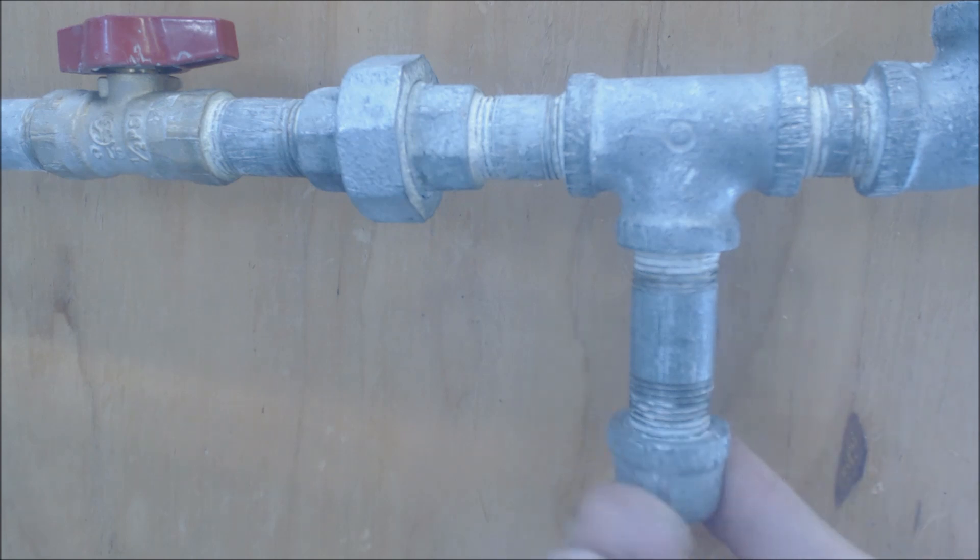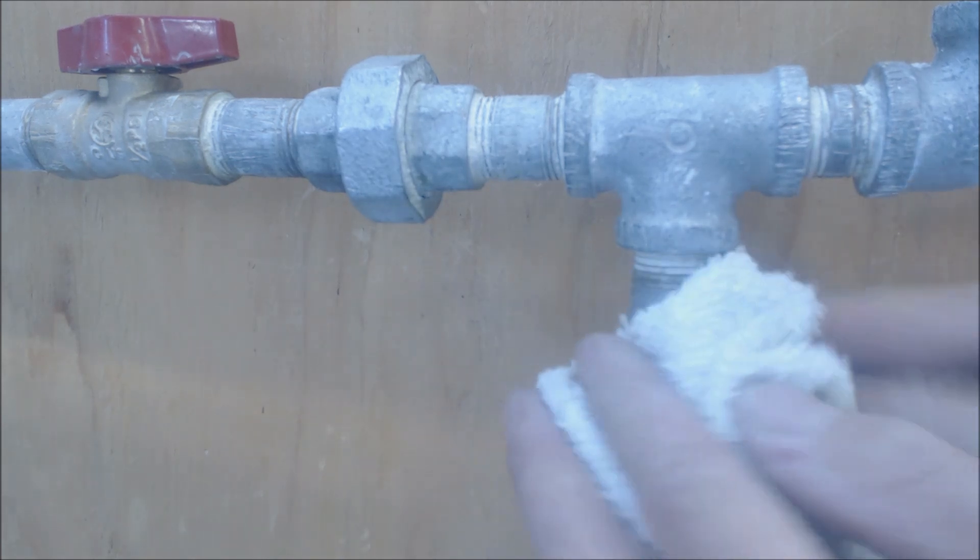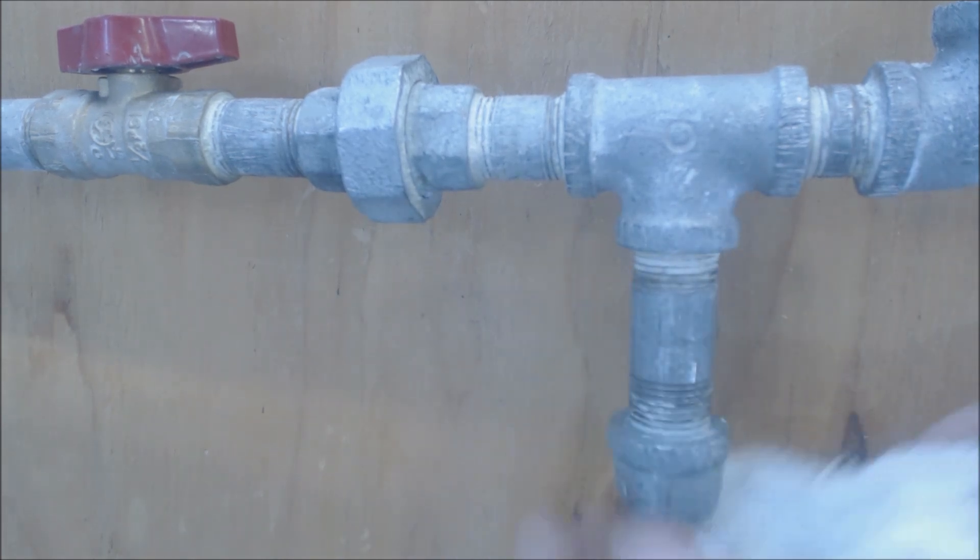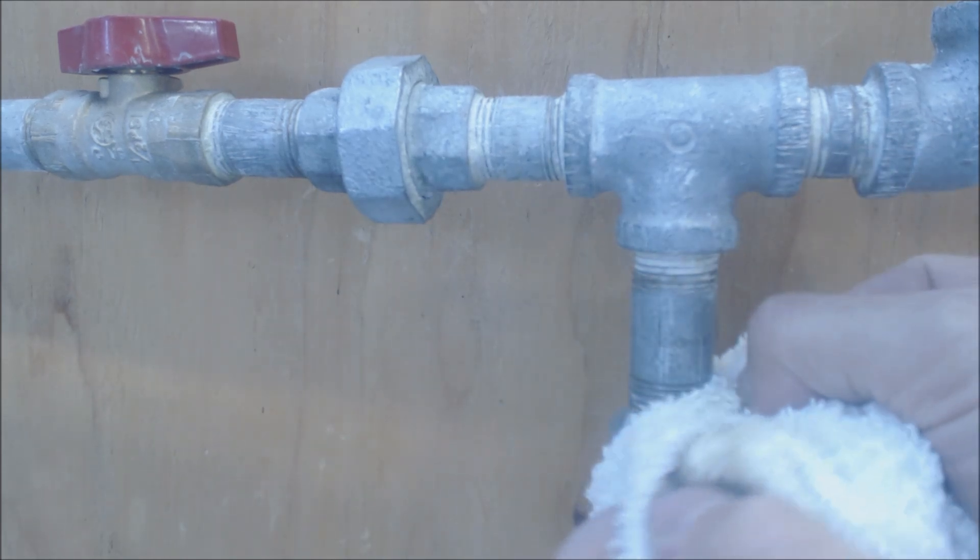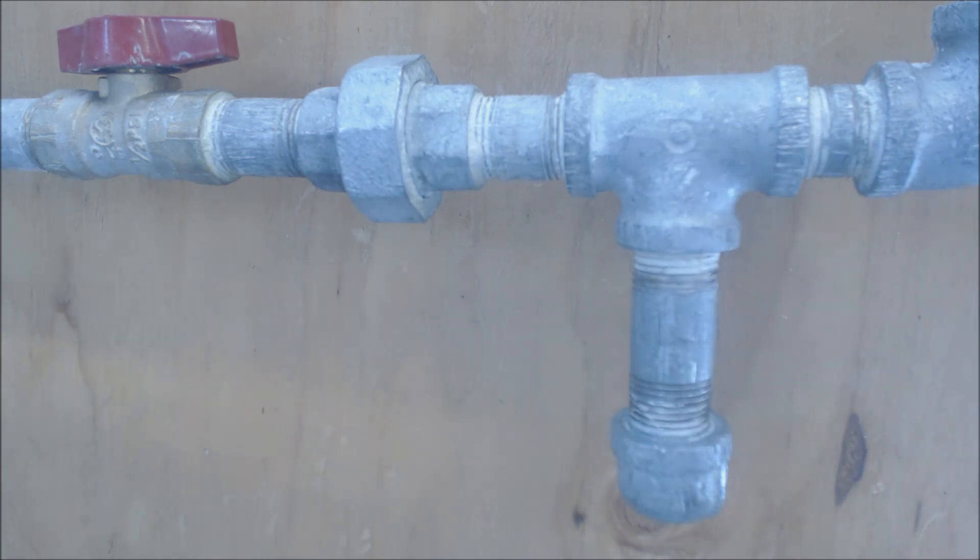I hear the gas. Let's just see if we see any bubbles. You see the bubble right there. That's with a non-corrosive bubble detector applied with a dabber. I'm going to wipe that off. We're seeing some of the bubbles forming right there. You still see the bubbles.